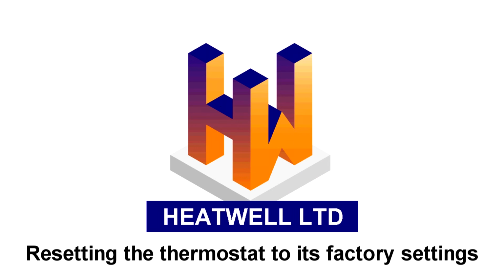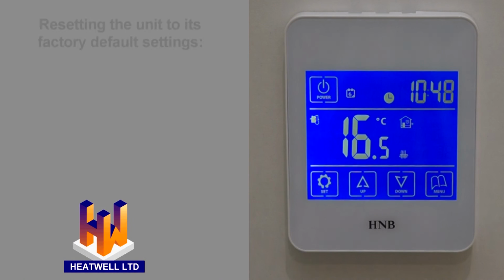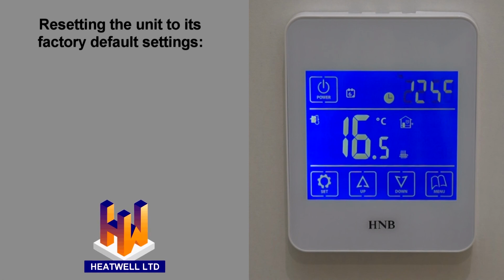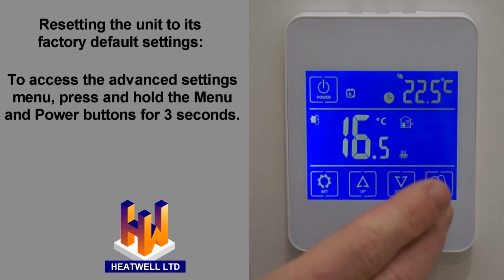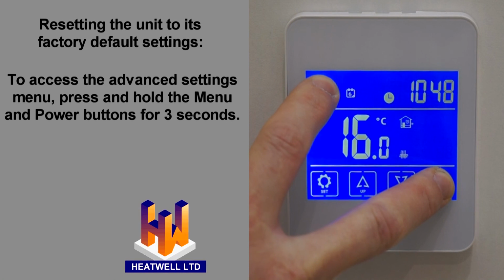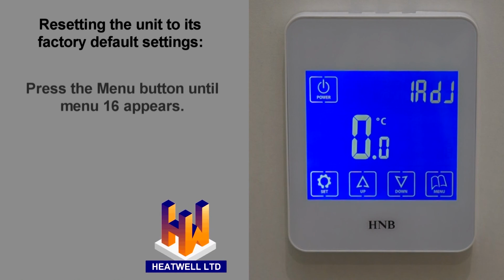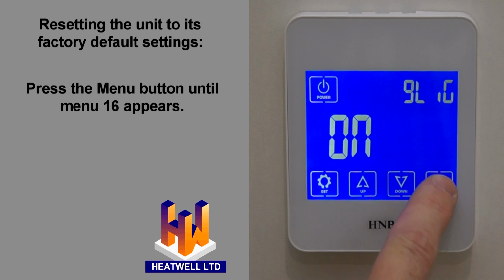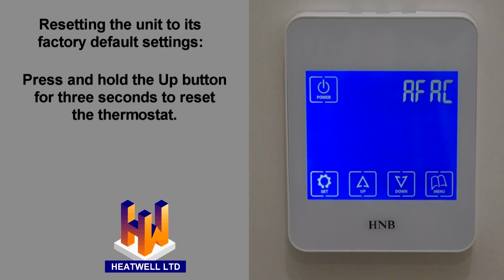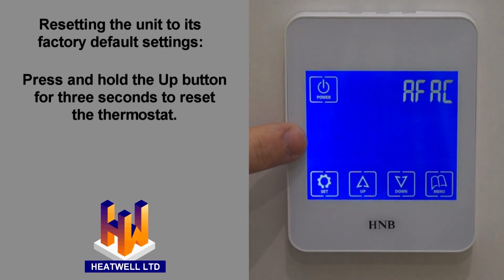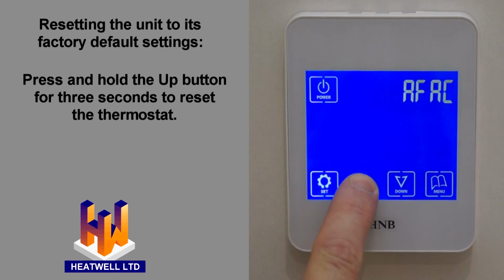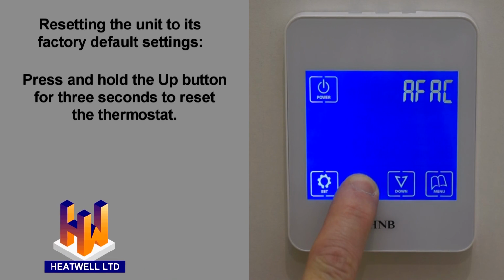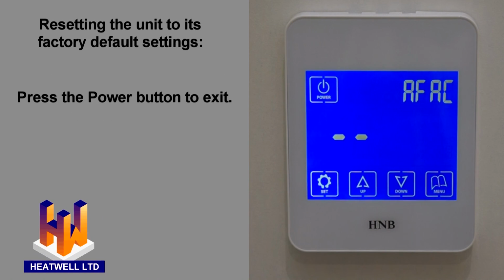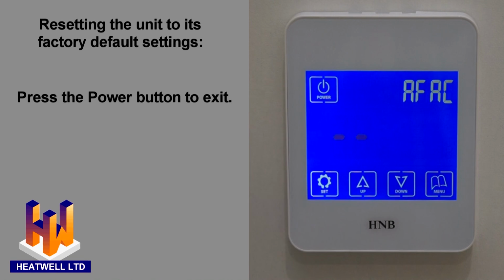Resetting the unit to its factory settings. To completely reset your thermostat to its original default settings, enter the Advanced Settings menu by pressing and holding the Menu then Power buttons for 3 seconds. Then press the Menu button repeatedly until menu number 16 appears. A single dash will be displayed on the screen. If you are certain you wish to reset the thermostat, press and hold the up arrow for 3 seconds. The unit has now been reset. Press the Power button to exit.